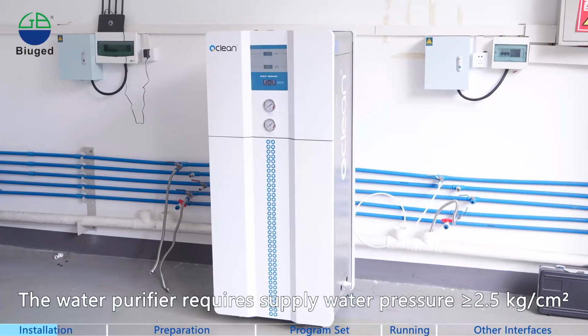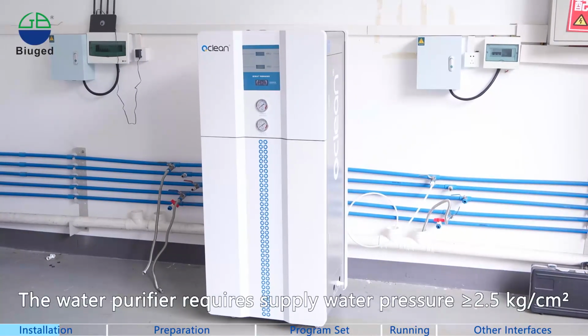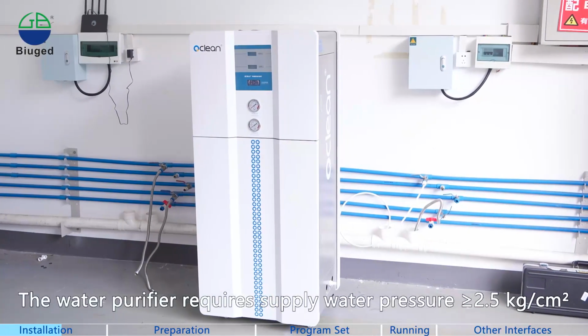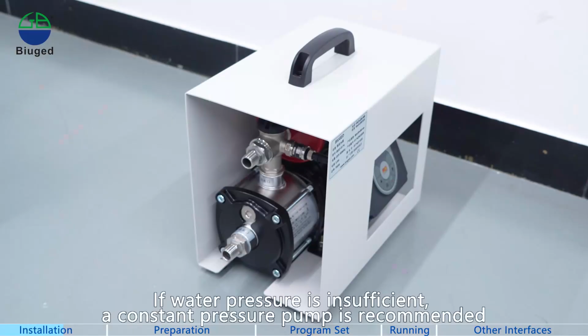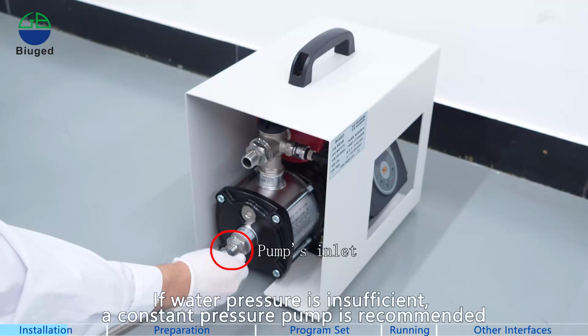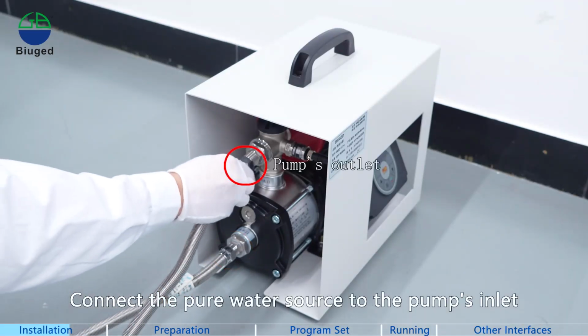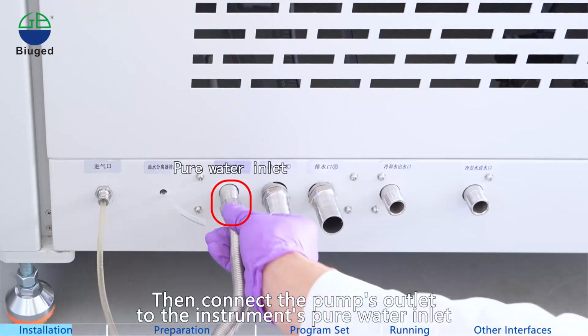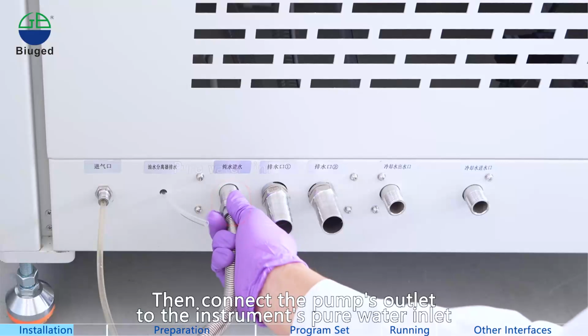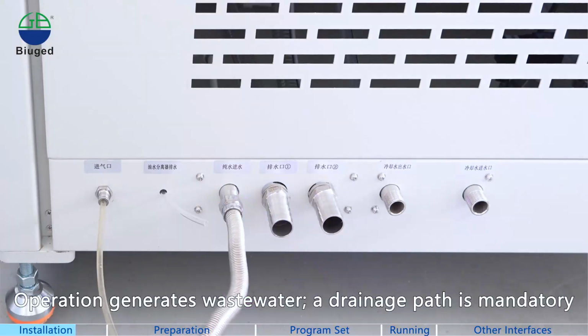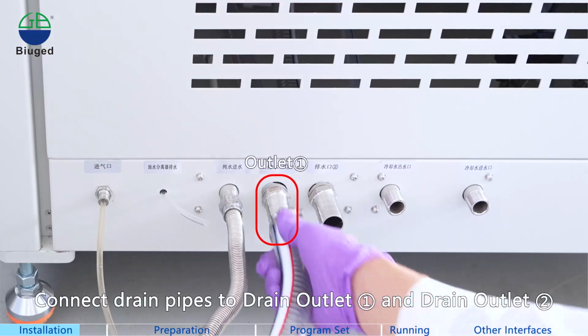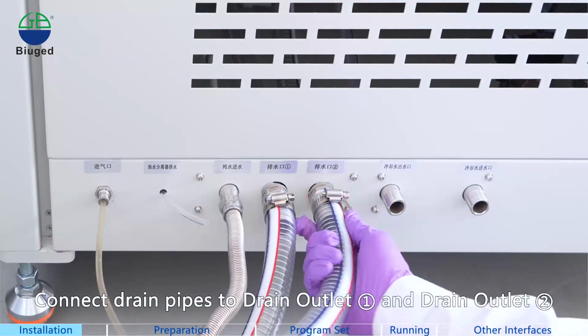The water purifier requires supply water pressure greater than or equal to 2.5 kilograms per square centimeter. If water pressure is insufficient, a constant pressure pump is recommended. Connect the pure water source to the pump's inlet. Then connect the pump's outlet to the instrument's pure water inlet. Operation generates wastewater. A drainage path is mandatory. Connect drain pipes to drain outlet and drain outlet.